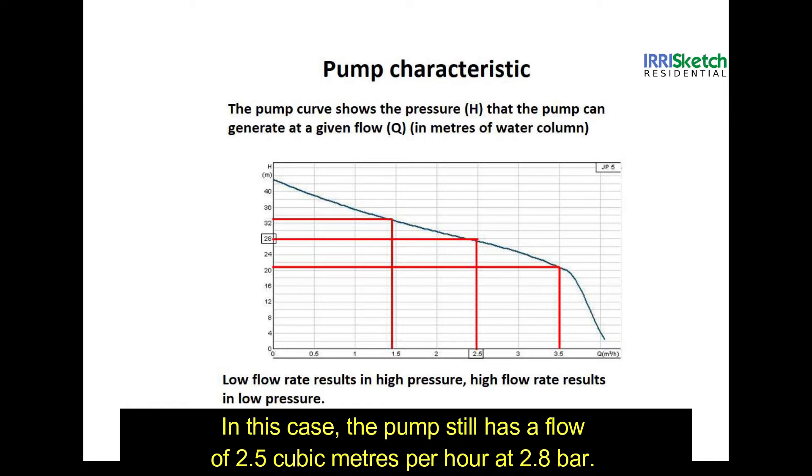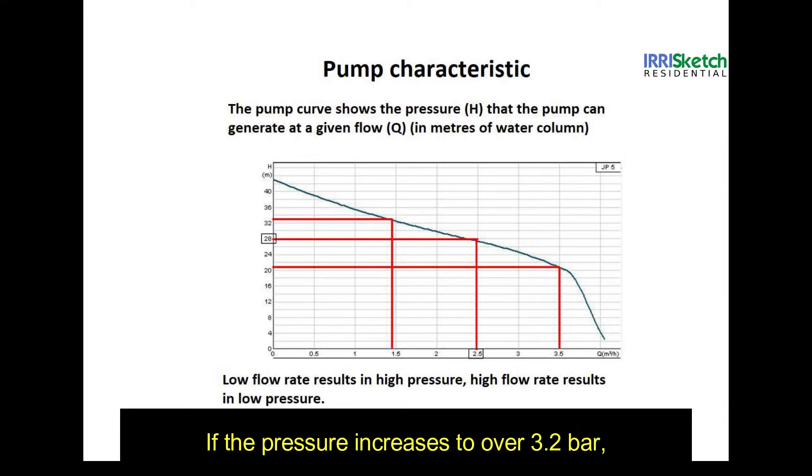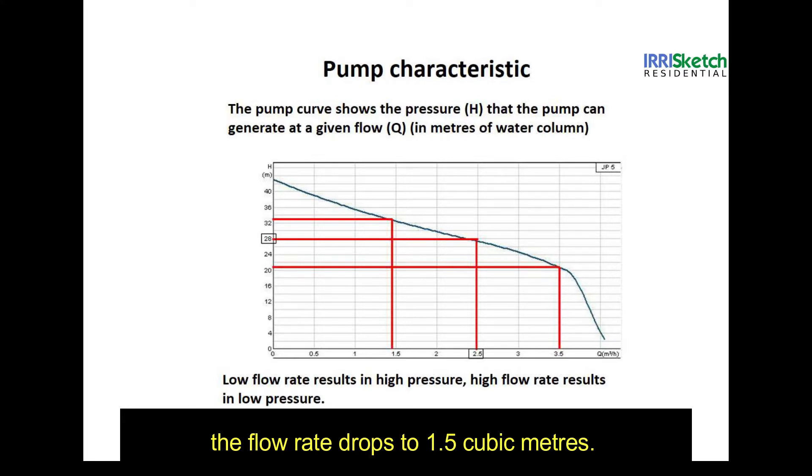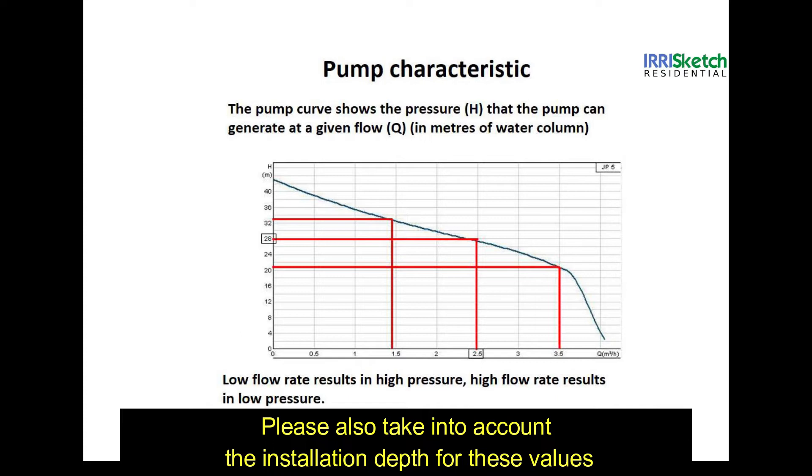In this case, the pump still has a flow of 2.5 cubic meters per hour at 2.8 bar. If the pressure increases over 3.2 bar, the flow rate drops to 1.5 cubic meters. Please also take into account the installing depth of these values.